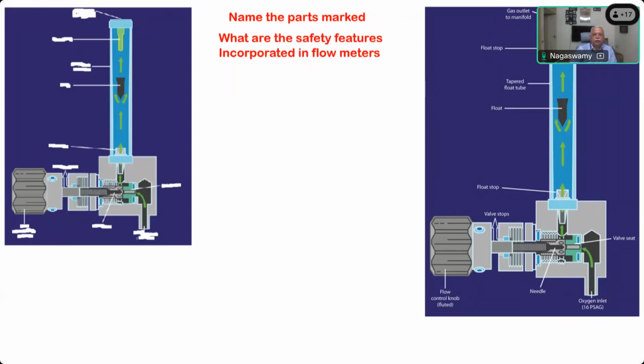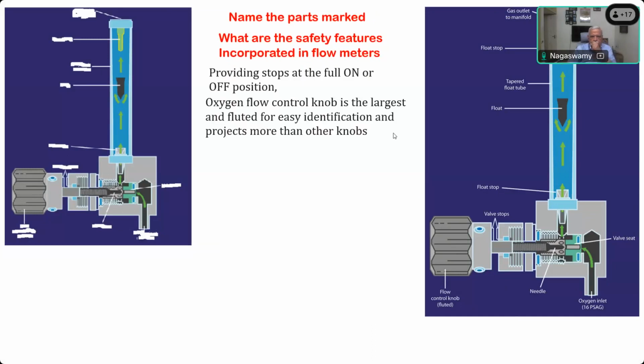Now, the fluorescent tubes are illuminated in the dark. They have anti-static material which prevents sticking of the bobbin or float. They have lower and upper stoppers so that the bobbin does not fly out. Bobbin is visible all the time. Providing stops at the full on or off position. Oxygen flow control knob is the largest and fluted for easy identification, and it projects more than the other knobs.